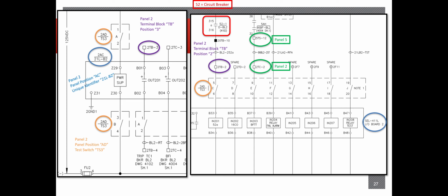52 is always going to be the circuit breaker identifier. It's labeled 52 everywhere I've seen. Another example for the naming conventions, 5HA, that's going to be in panel 5, and those two open contacts that run in series together, that is usually a lockout contact identifier. And like I said, lockout relay.